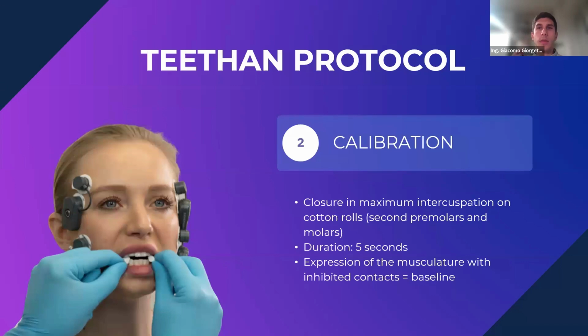The protocol consists of an initial calibration phase, which is necessary to set the machine on the patient. To do this, you need to place the cotton rolls between the patient's arches between the fifth and sixth teeth. The patient should then clench for a maximum of 5 seconds on these cotton rolls. In this way, we record a baseline, which is the best activity the patient can express unaffected by dental contacts. All subsequent tests will be compared to this result.